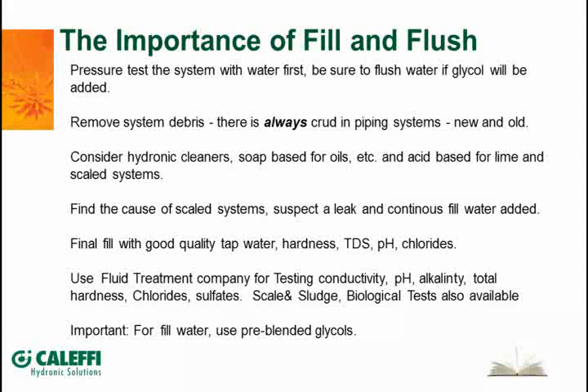So we'll start with the steps here that I would go through on a system. Of course, you want to pressure test the system first. I used to prefer to use water, unless it's in a condition where it's going to freeze and you have to use air because you don't want to leave it on the system overnight. If it's outside or if it's a snow melt or something like that, you'd have to use air in the winter time. But water's good because you can flush out some of the dirt and debris that's in there, and it's also easier to spot a leak with water.